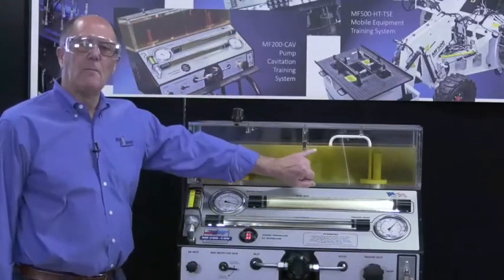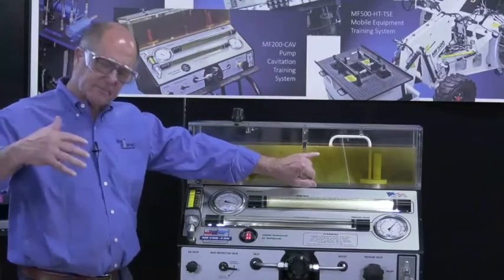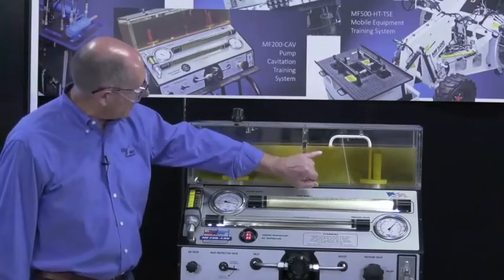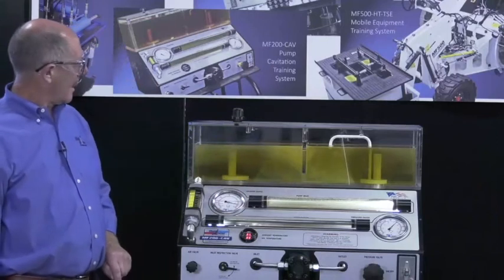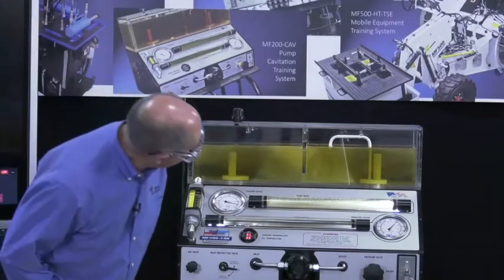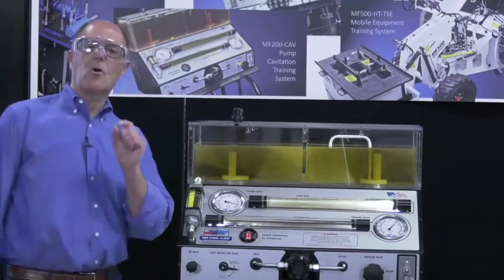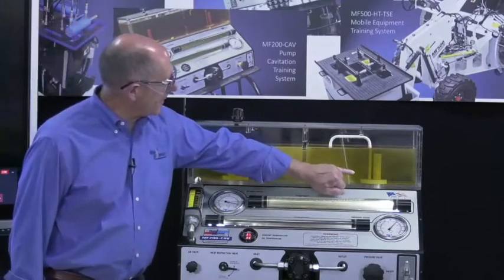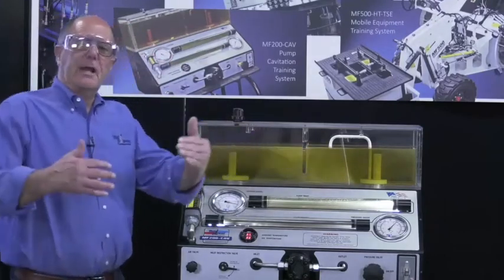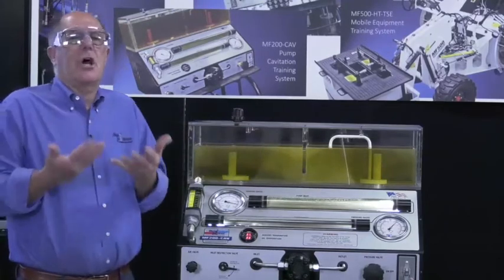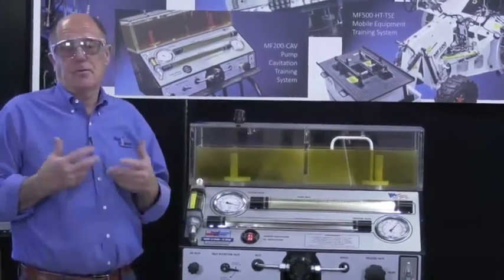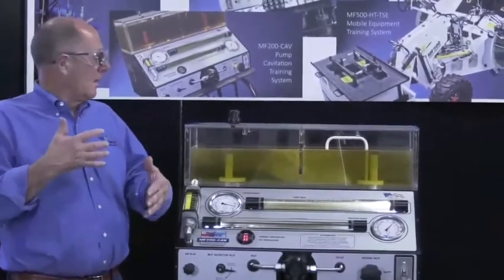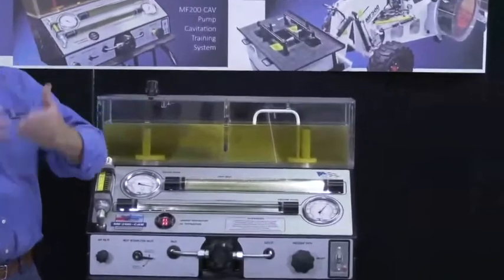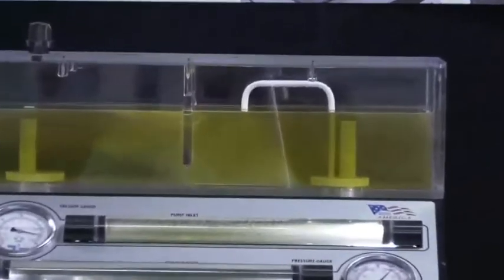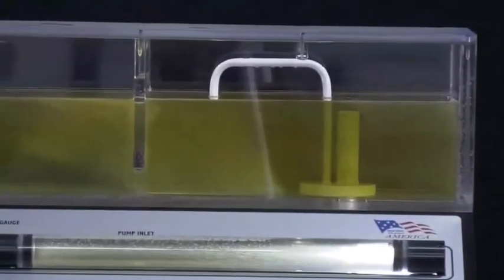My intake is almost out of the oil. Sorry, my return is almost out of the oil. About a quarter of an inch to go. Notice in this area here, you'll just get a huge amount of turbulence. And of course, as you well know, or maybe not, this is going to start creating an air condition. It's going to introduce air into the system, and you're back to square one, back to pseudo-cavitation.